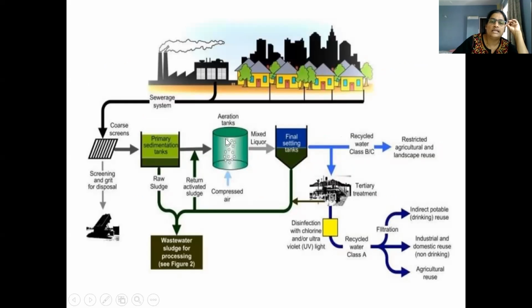Okay, so aeration can be performed in different ways. In water supply engineering, we saw the cascade aerator and fountain aerators, but here usually surface aerators are used. Big aerators are installed, with blades that rotate very fast on the surface. Because of that, the maximum amount of water comes into contact with atmospheric oxygen, and atmospheric oxygen gets dissolved into water.